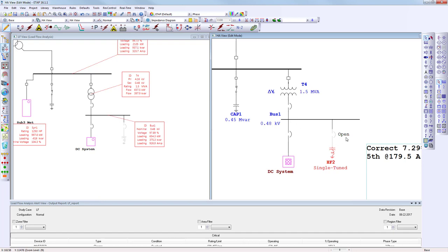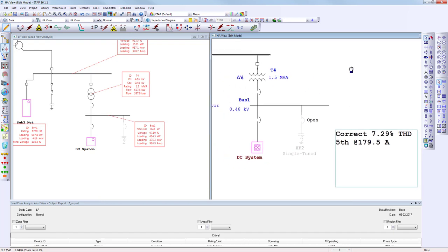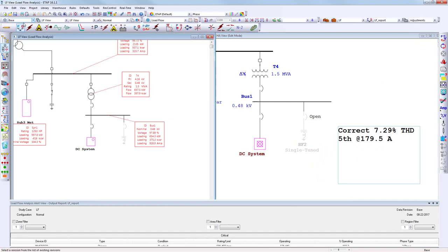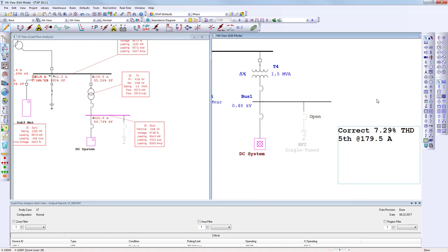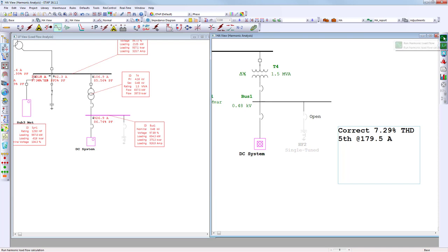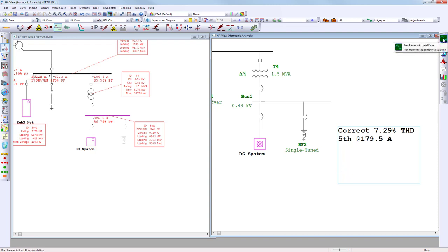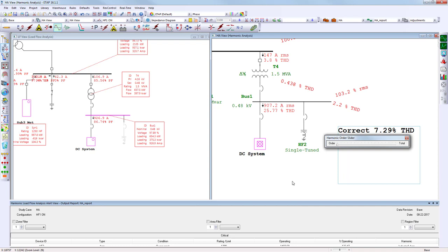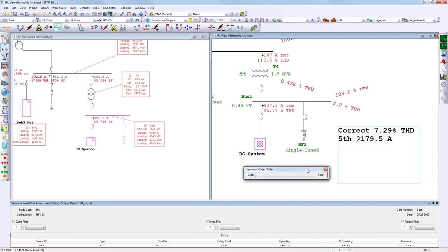To show the before and after results: with the load flow on the left and harmonic analysis on the right, I bring the filter online and run the harmonics analysis. The total harmonic distortion has now dropped from 7.29% down to 2.2% — well within acceptable limits.